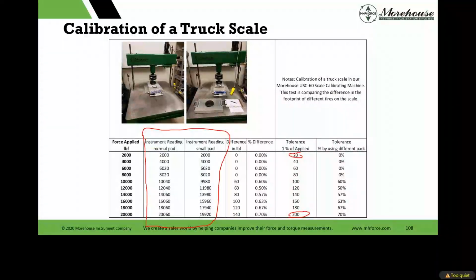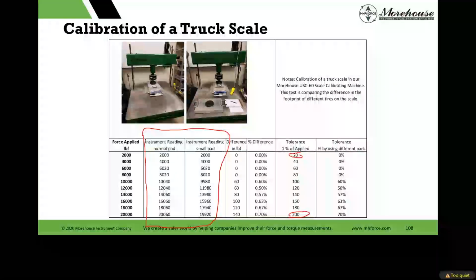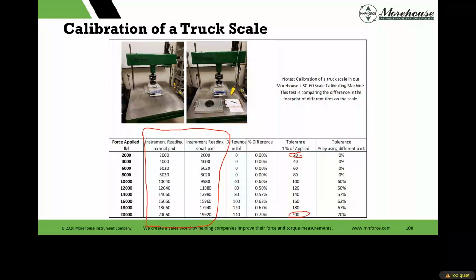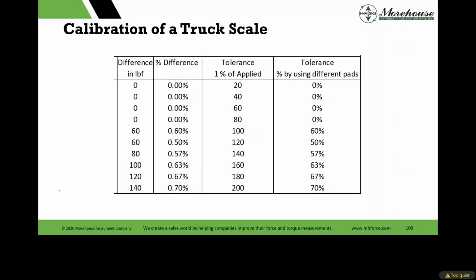The difference between those two was about 70% of the tolerance. Like I said, a 140-pound difference, that's over here. So that eats up a large portion of the tolerance and does make a difference. And this is a better zoom in of that, the tolerance, the difference in pounds. You can see not much difference at the low forces, and as you got to the high forces, it was about 70%.